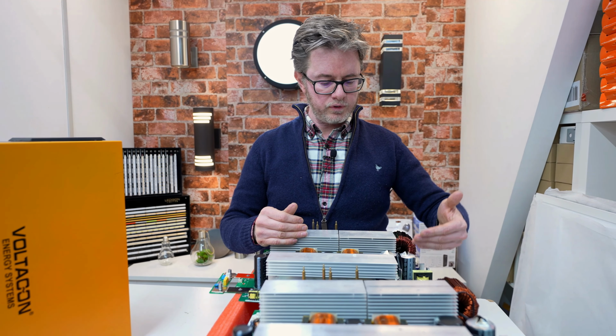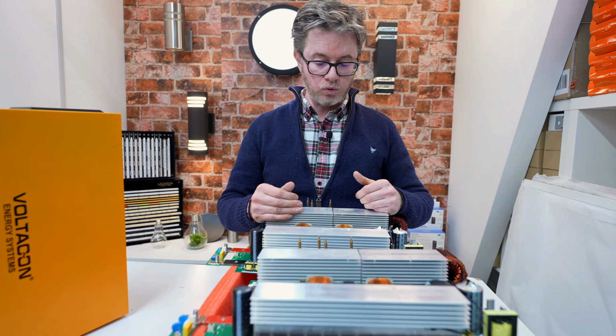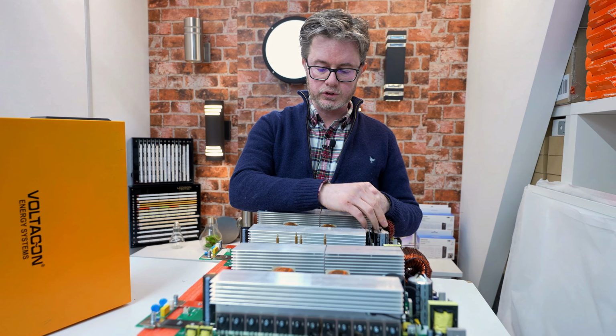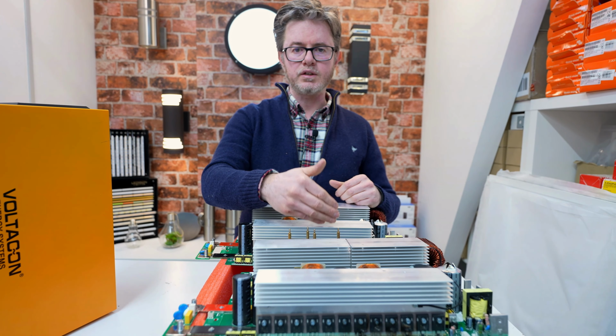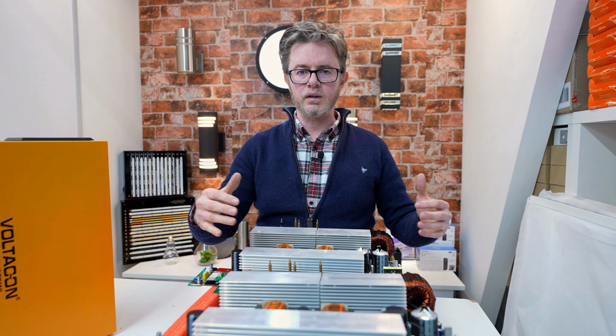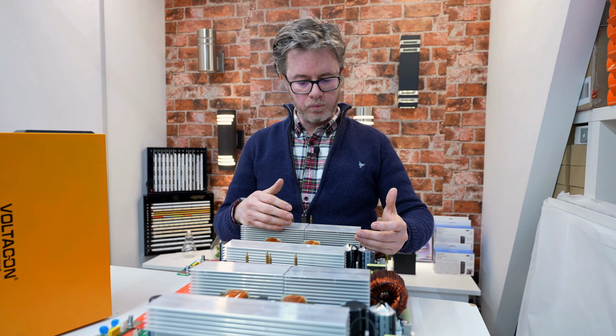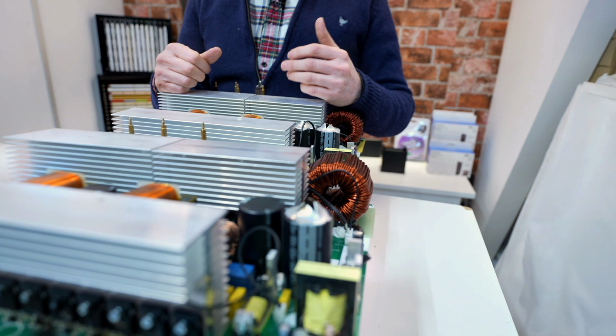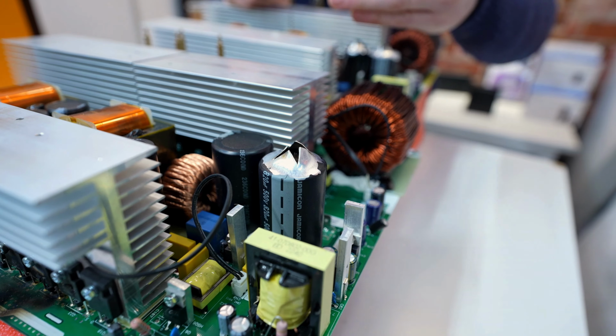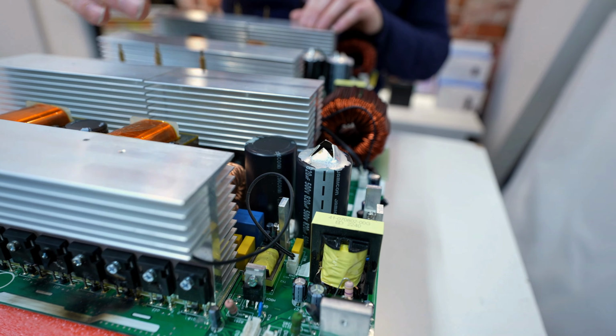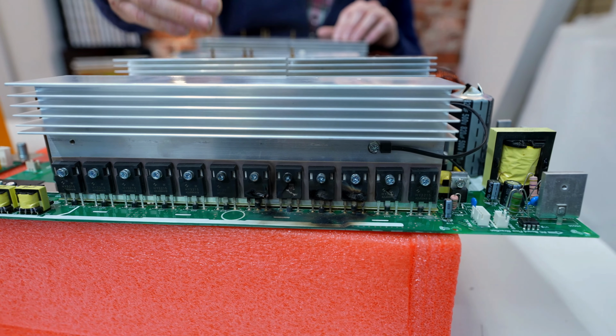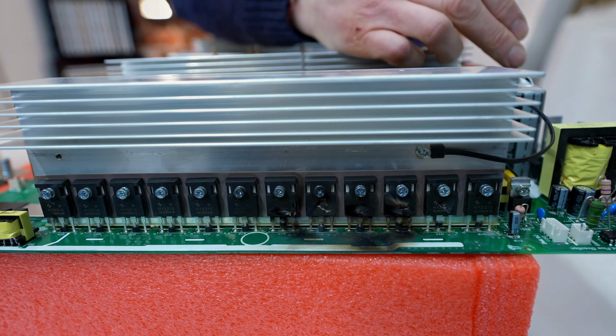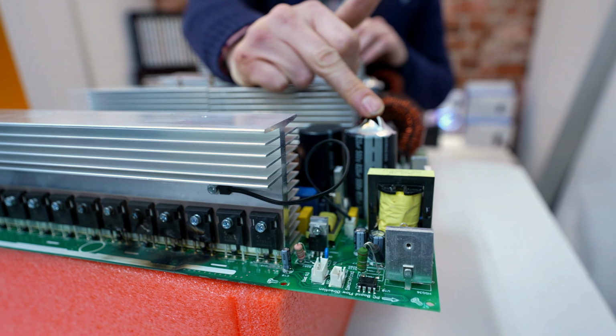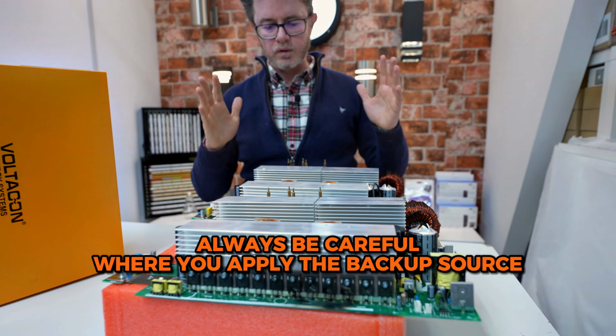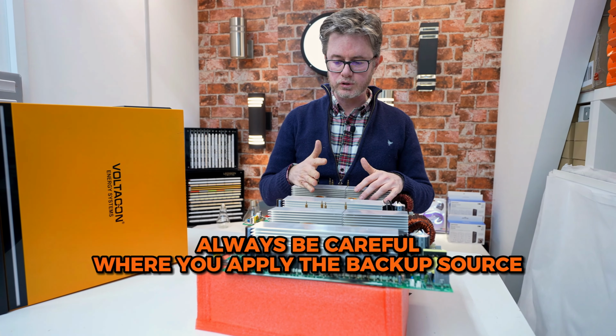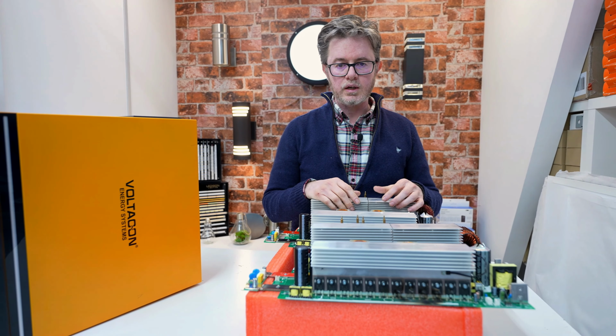So you overcharge the capacitors from the output, and overcharging the capacitors is going to modulate the IGBTs wrongly as well, with the wrong voltage, and that's why you get a very loud bang from both devices. It's not a coincidence that the capacitors explode and, at the same time, in a few milliseconds, even the IGBTs blow up, because the IGBTs are modulating the DC voltage of the capacitor. So if they modulate the wrong voltage, they are going to blow up. So number one, always be careful where you apply the backup source. You shouldn't connect it wrongly to the AC output.